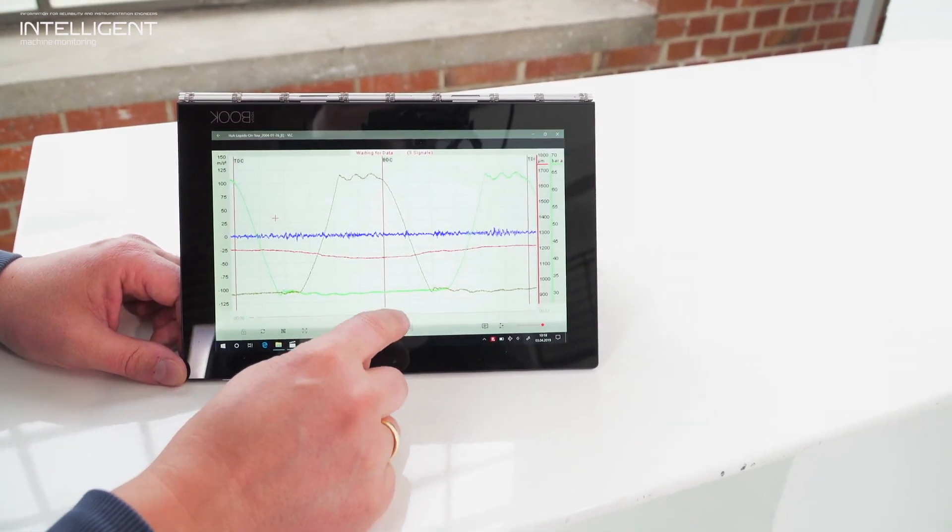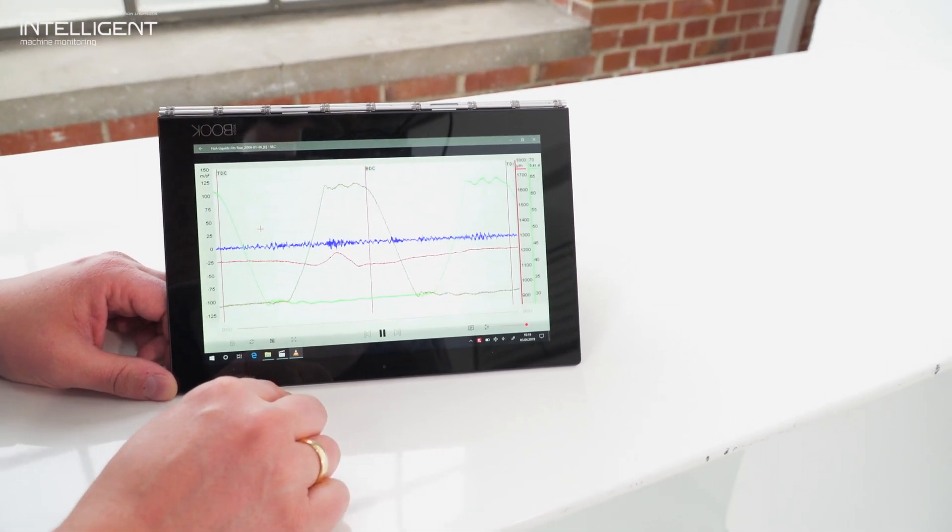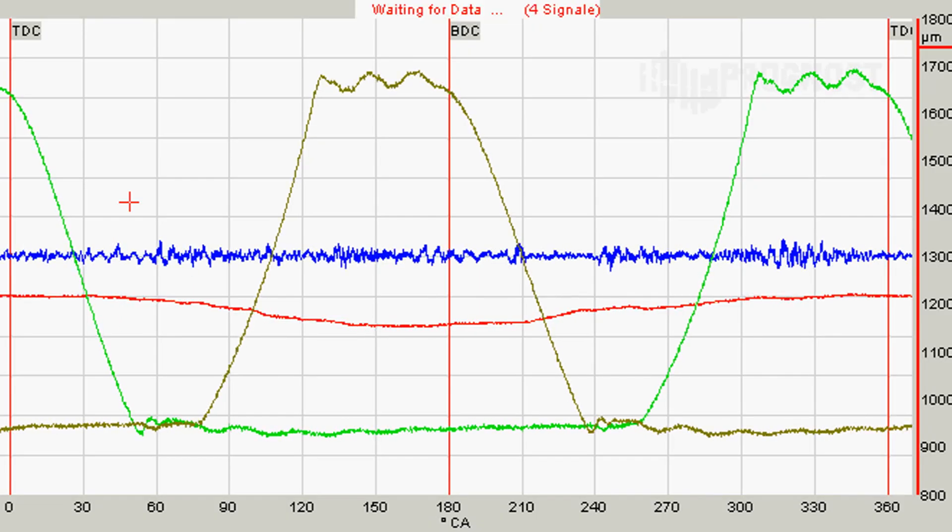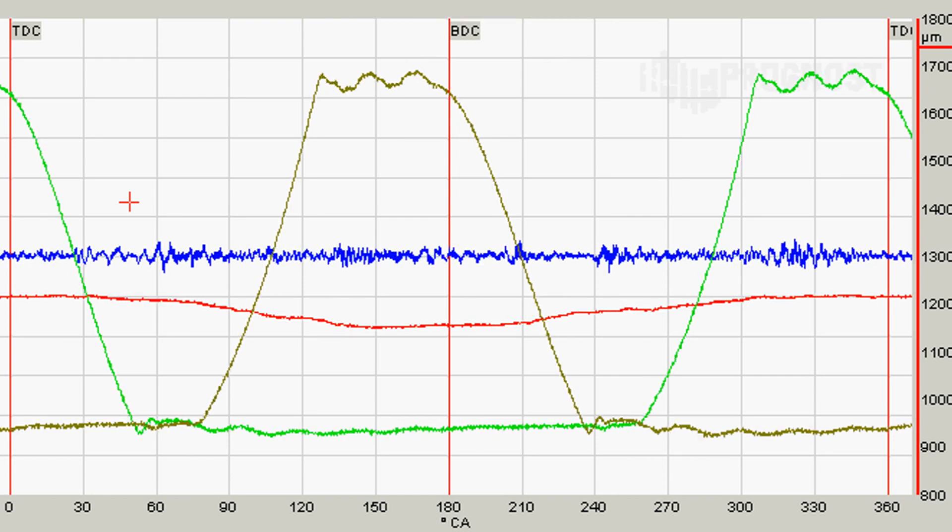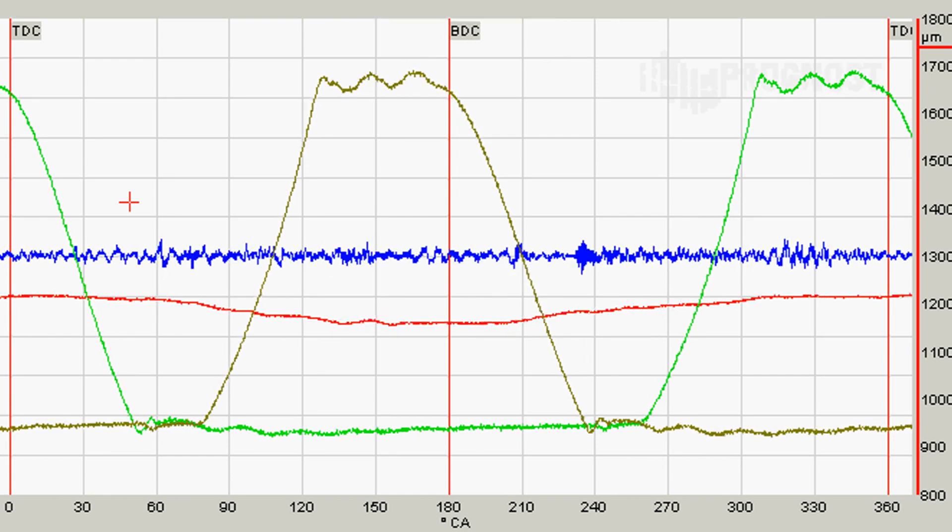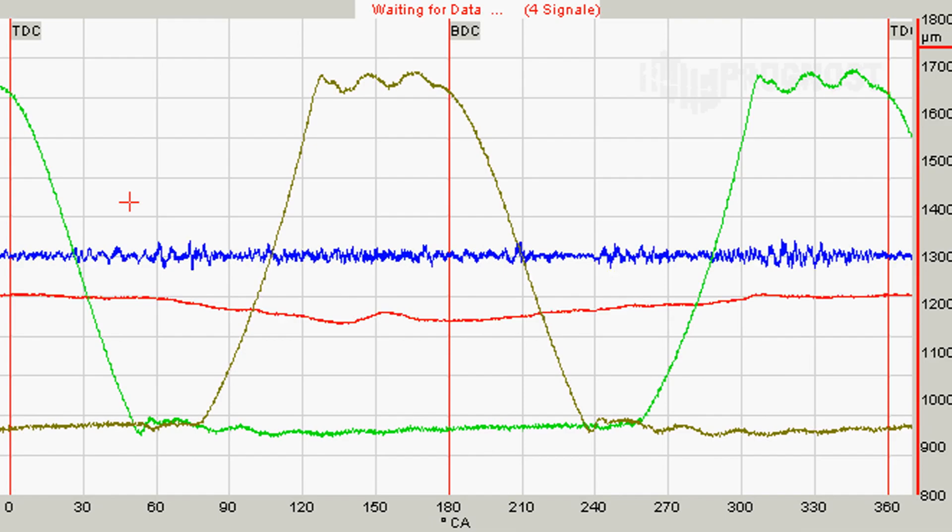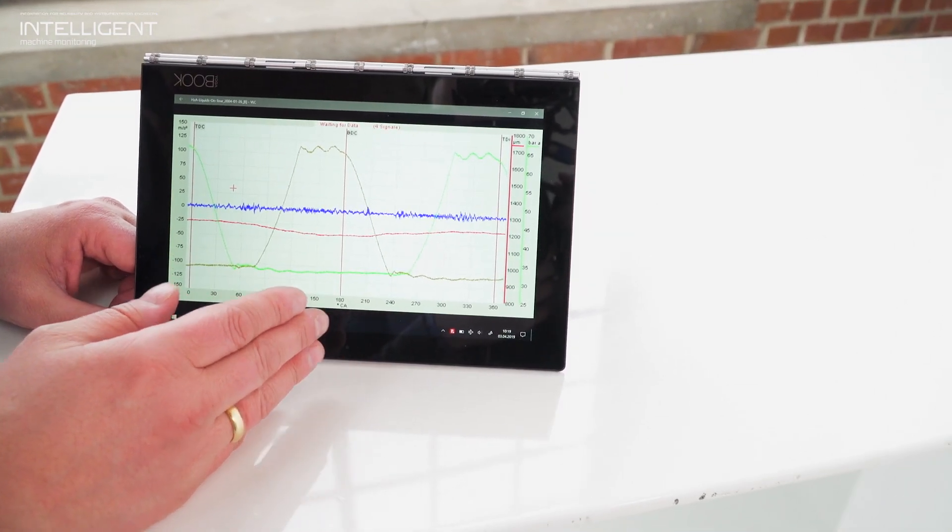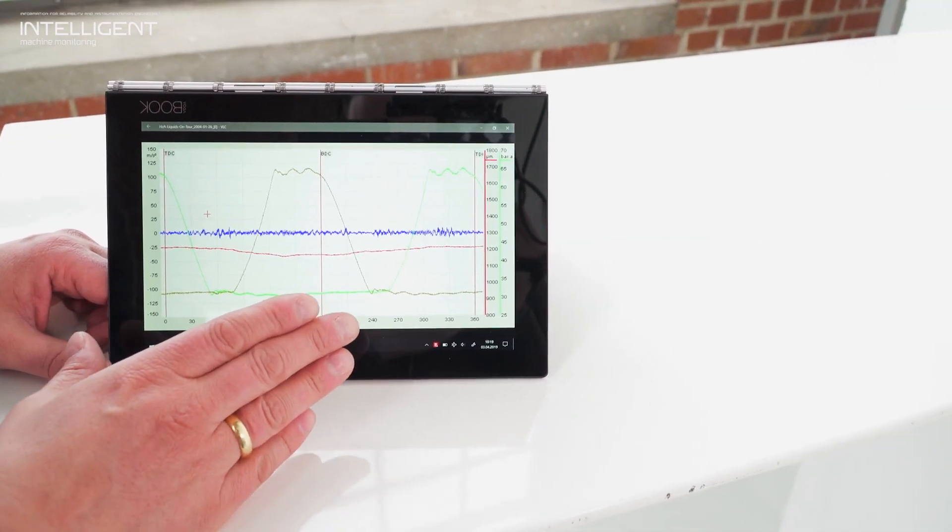So as explained, we will run the compressor with 420 rpm. That means you will have only a short time which the liquid carryover occurred. Everything is in normal mode currently.